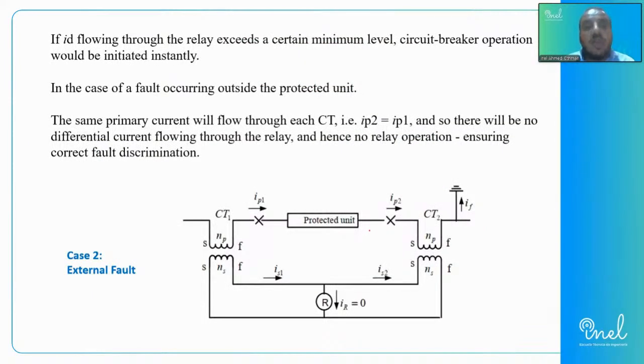And here also we confirm that if there is a certain current flowing through the relay, and such current exists at a certain level, the relay will give a tripping order to the circuit breaker, and the circuit breaker operation is initiated instantaneously. And in such a case, we are protecting our transformer.